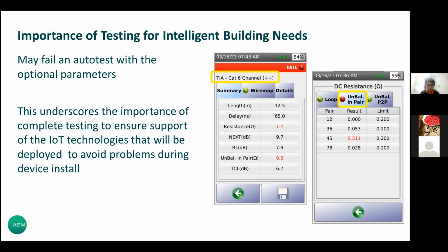So pass and fail helps to give you attention. Hey, your cable has some problem with the DCR resistance. It may not be supported. It's telling you it may not support PoE. Don't worry if you get this. We can troubleshoot and do rectifications. Maybe the failure comes from the patch cord, maybe from the connector, which can be resolved. Important for those involved in building applications and ELV systems running on the same UTP cable, you have to take note of this.